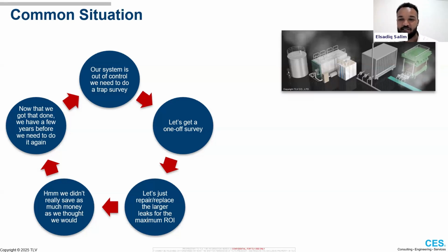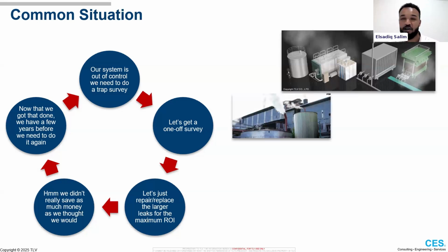And then the natural decision is that we don't need to get another one for another few years. And then the cycle repeats itself. That's a common situation, and it leads to images like this. The difference between the top image and this second image is that the second image is a live steam loss. So this is not steam from your condensate system. This is steam from your steam system. So directly, you'll feel that on your gas bills, on your boiler directly.